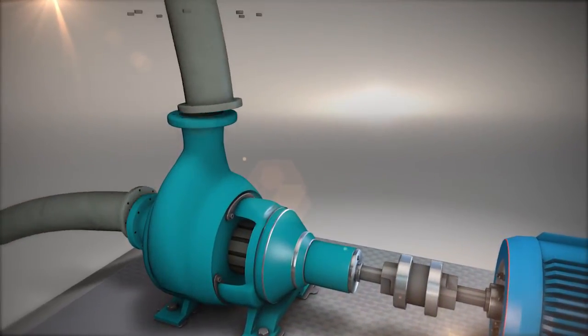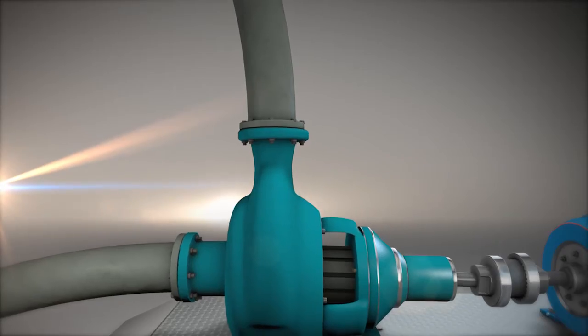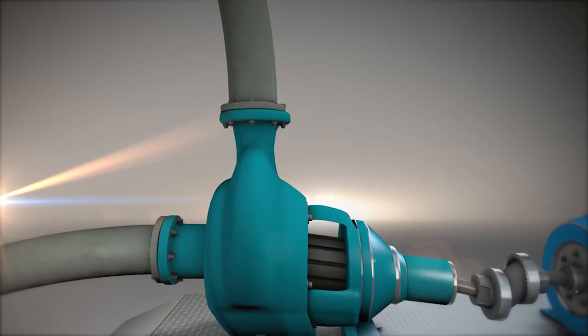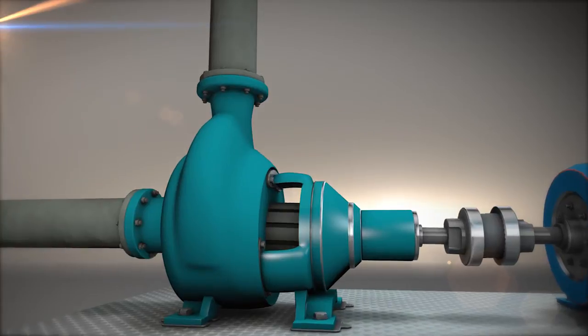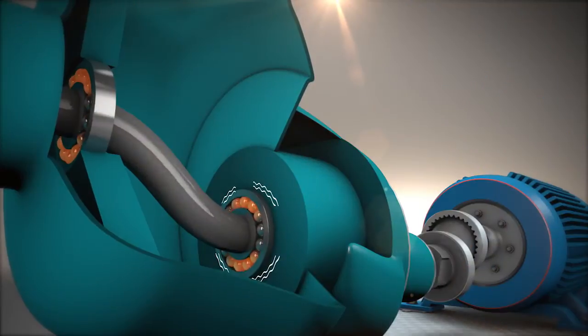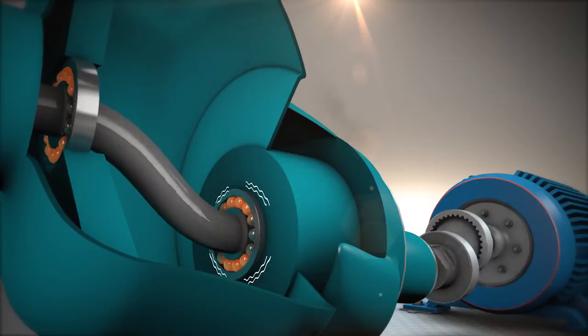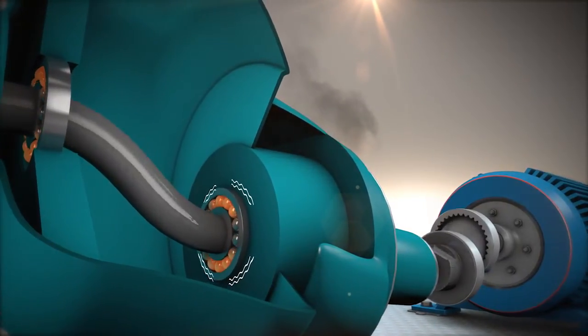The pipe stress pulls on the pump flange. This forces the frame of the pump to distort vertically and or horizontally. The resulting deflection of the pump casing results in internal misalignment of the bearings, inducing vibration and premature failures.